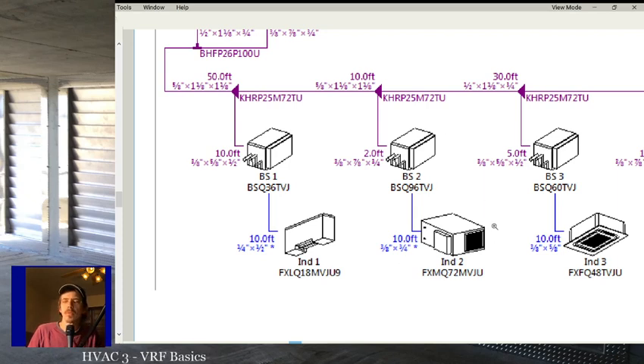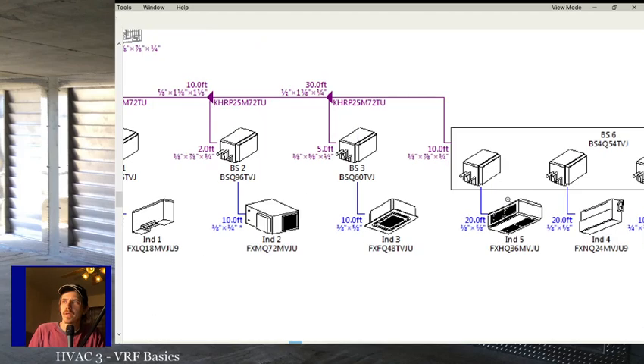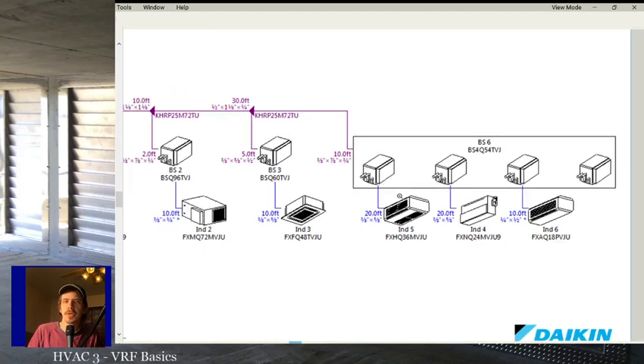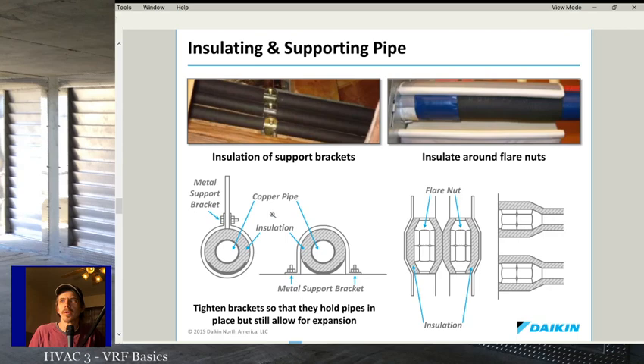I can't remember what it was, but I remember one time we did have to keep the line set a little longer from one unit to another. I think it was just so we could keep the minimum distance, and instead of like a 3-foot run, it ended up being a 10-foot run. But that was because we needed 2 feet between two branches, if I recall, and it's just how it turned out. There's a bunch of other piping considerations to think about.